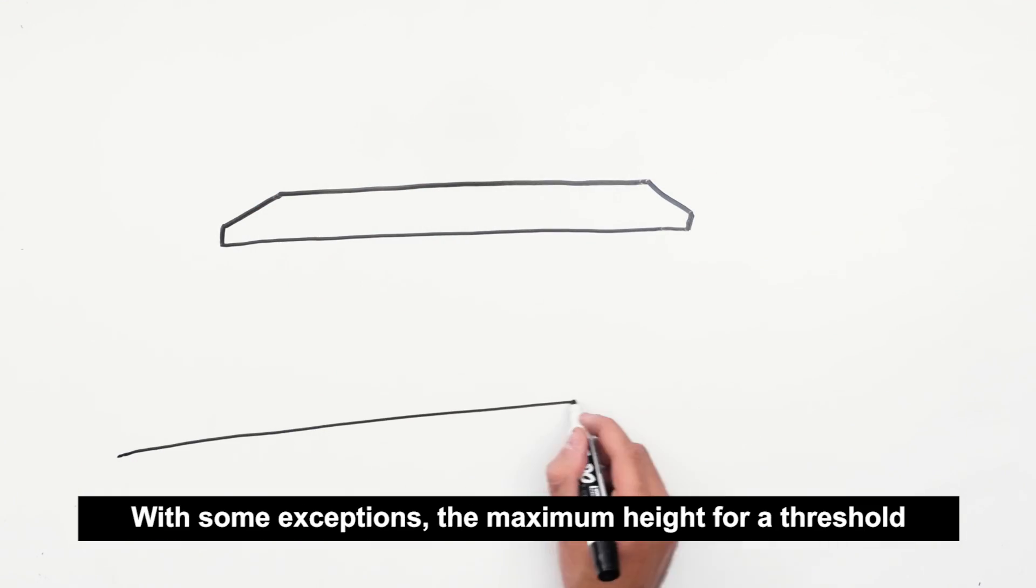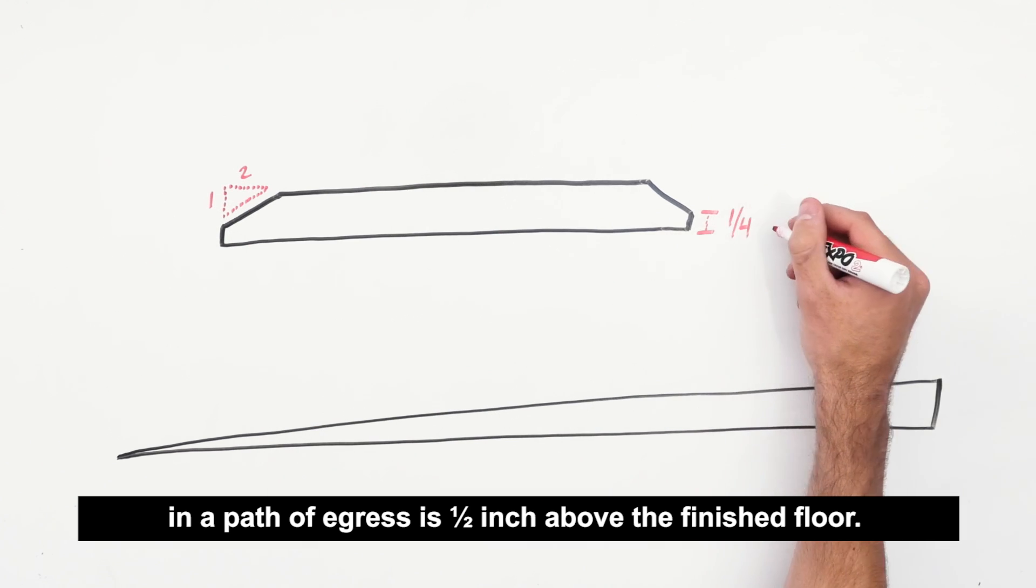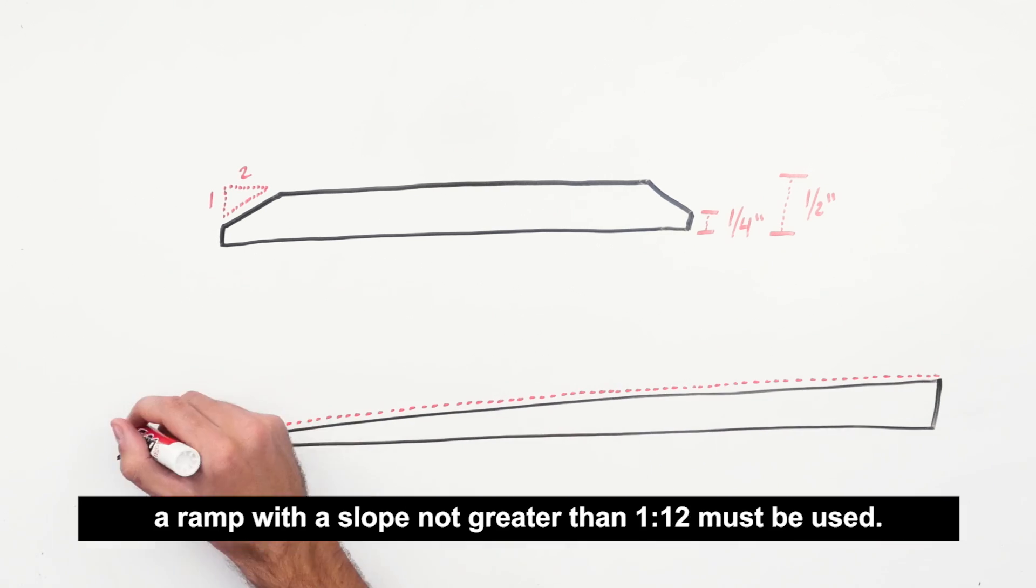With some exceptions, the maximum height for a threshold in a path of egress is one half inch above the finished floor. A rise of up to one quarter inch may be vertical, and a rise of one quarter inch to one half inch must have a slope not greater than one to two. If the rise is more than one half inch, a ramp with a slope not greater than one to twelve must be used.